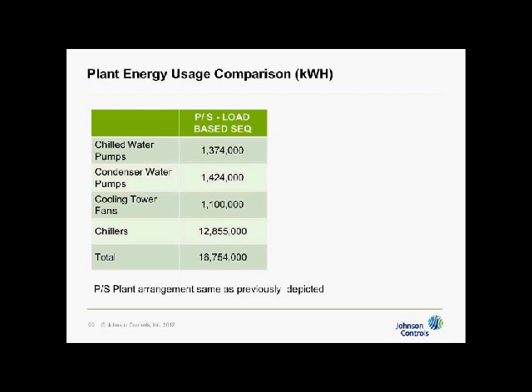First, we analyzed the primary-secondary plant that was described earlier, and on the assumptions just given, the chill water pumps use approximately 1.3 million kilowatt hours, a little bit more than that, 1.4. The condenser water pumps used 1.4 million kilowatt hours. The cooling tower fans, 1.1 million kilowatt hours. The chillers, even though they were VSDs, used 12.9 million kilowatt hours.